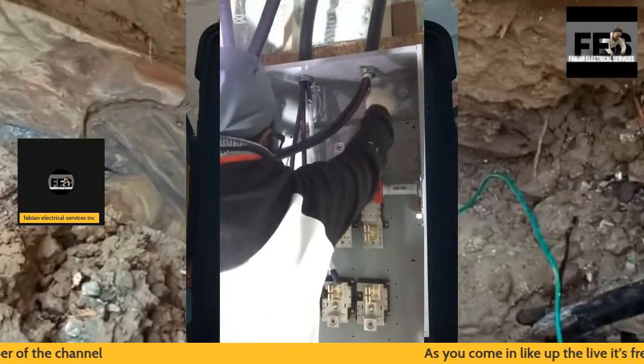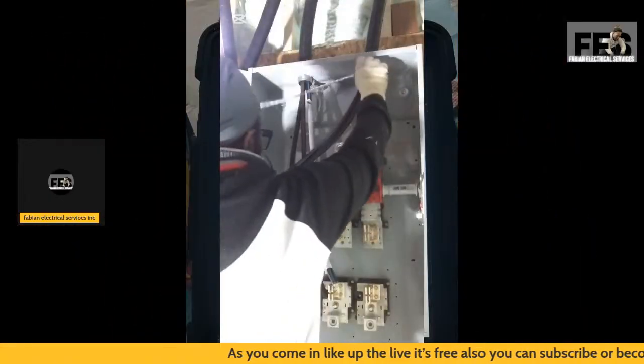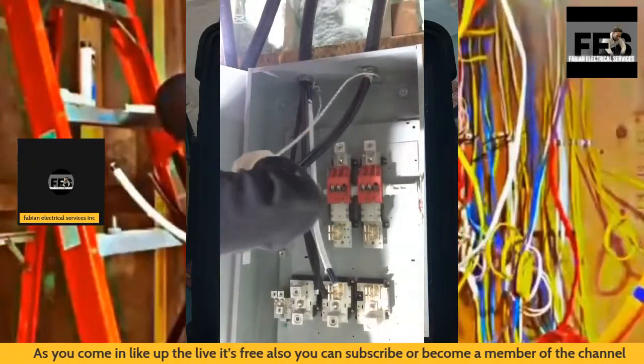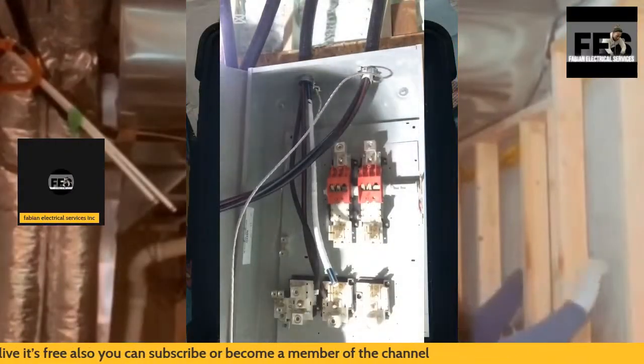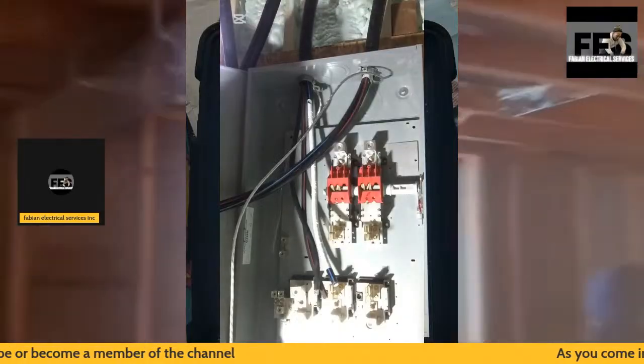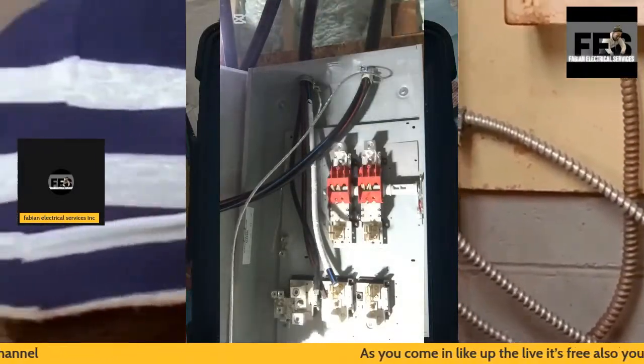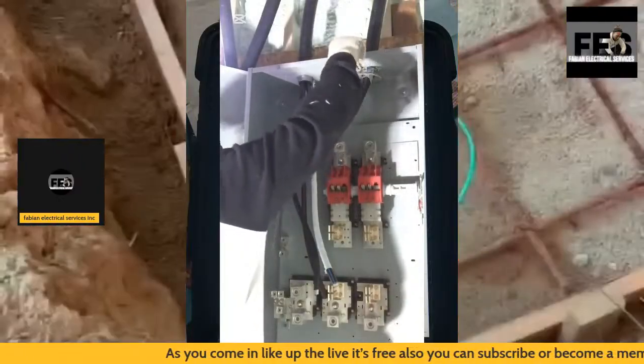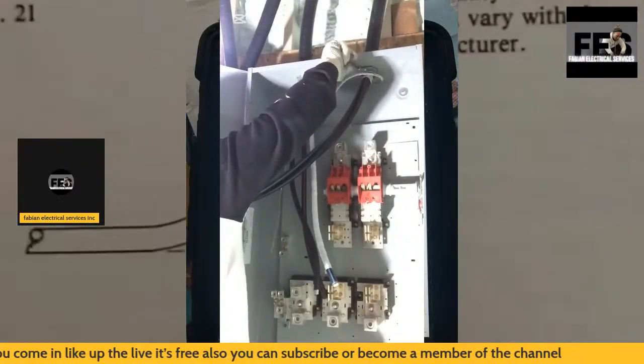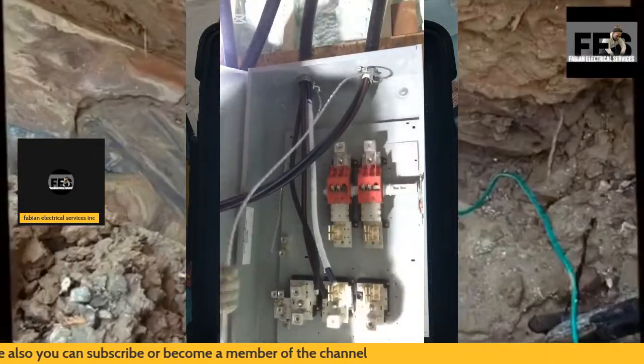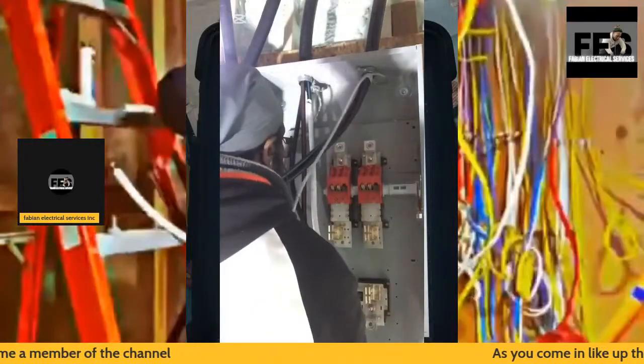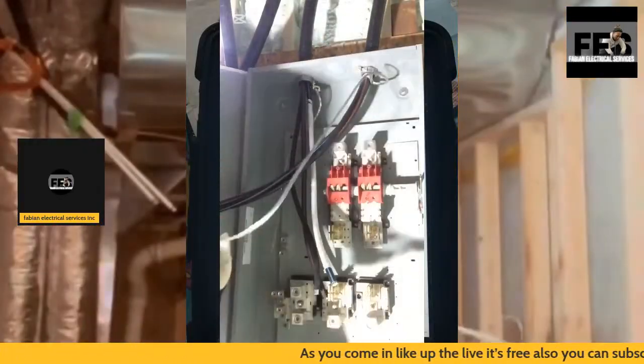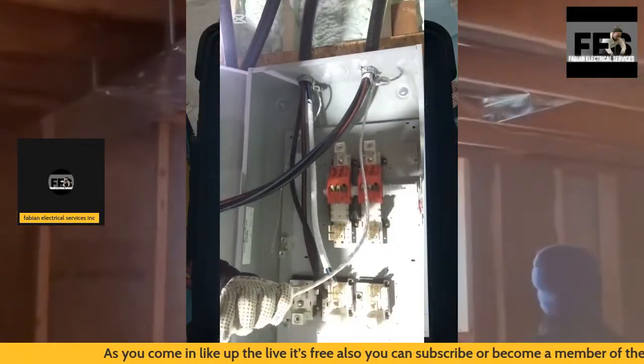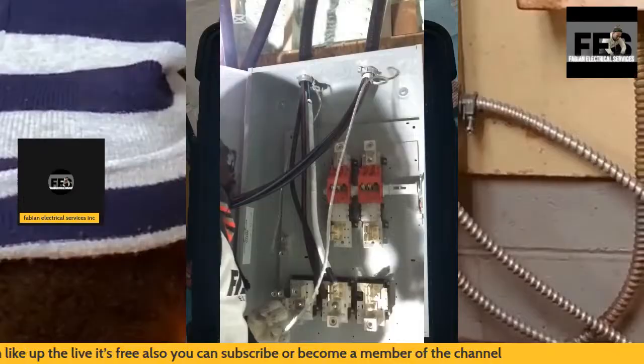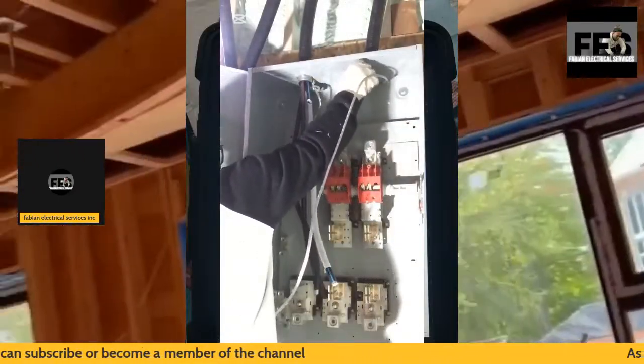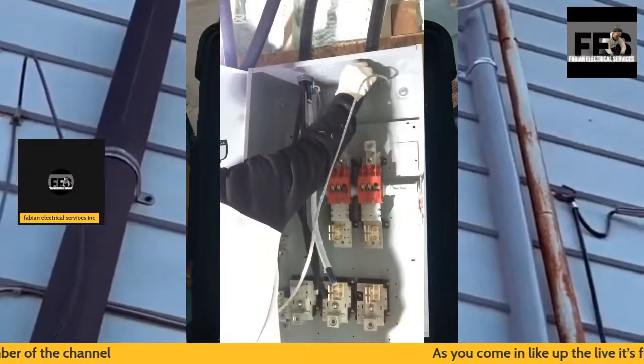So as you can see, the reason why I like to keep the white paper on is it simply helps with the cable. As you can see, the cable is locked in place. Once you disassemble that, it gives you a lot more problems getting the cable inside of the connector. So that's why I always make sure I land my cables inside of the disconnect, inside of the connectors, and I make sure I remove that. Then what I go ahead and do is my groundings. So this is a grounding and bonding installation. There are two different things when it comes to bonding and grounding. They serve two different applications, so never get that confused.